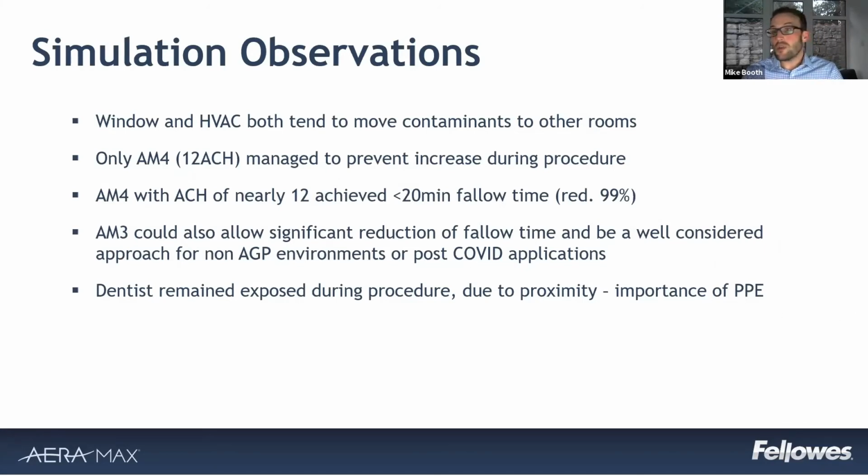What you might also consider is trying to get to those 10 to 12 air changes by using 2 solutions, a fixed wall-mounted 6 air change per hour solution, and then a portable 6 air change per hour solution as well. And that could be really complementary to have side by side whilst these restrictions are in place. But then post-COVID, you may want to spread that around in other areas of the practice as well.